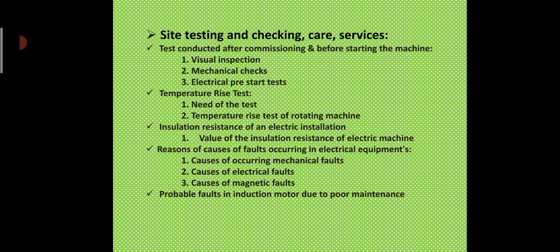The value of the insulation resistance of an electrical machine. To measure the insulation resistance of the electrical machine, a megger of twice the rated voltage of the machine is used. For 440 volt motors, a megger generating 1000 volts is used. Insulation resistance is measured between each phase and body. The value of this resistance should not be less than 2 megaohm. While measuring the insulation resistance, the temperature is measured. Then the value at the specified temperature is calculated and compared with the recommended value.